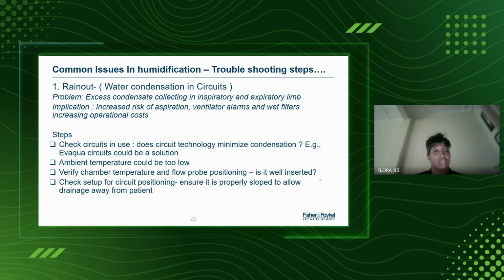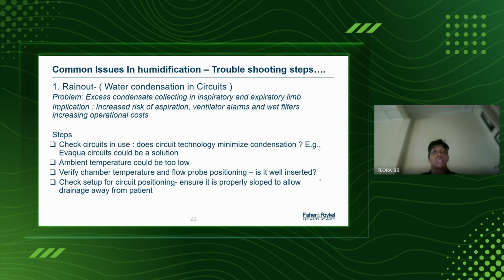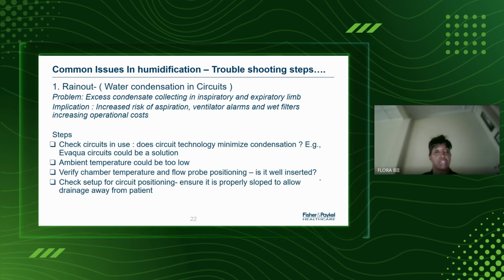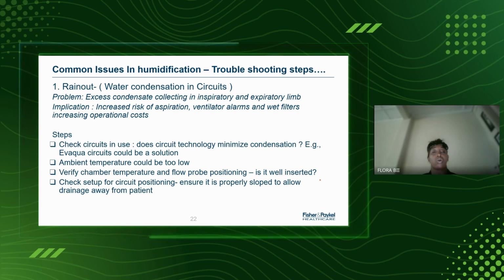Now, to the heart of the matter, you find that we do face a lot of issues when it comes to humidification, and it's important that we all understand how to troubleshoot these issues. A major one is rainout, where you have water condensation in the circuits. Now, the problem with this is that when you have excess condensate collecting in the inspiratory or even the expiratory limb, you find that the implication of that is that you'd have an increased risk of aspiration.